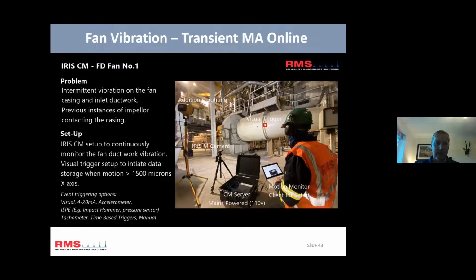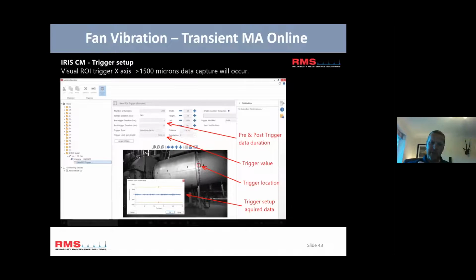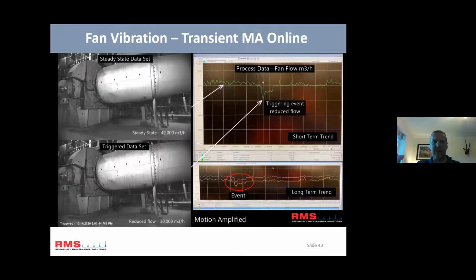So we basically set up the system, powered it with a little server, and this was the cool bit, we used a visual trigger. We looked at what the fan was doing as it was running normally, and then basically said to the system, if you see over this level, I want you to capture the data. We had it on there a week, and within a week it had nailed it two or three times.